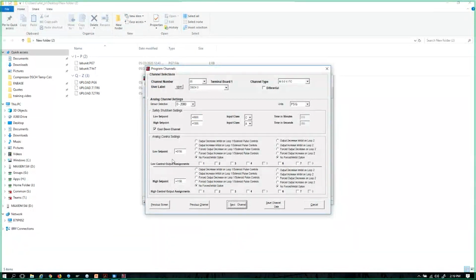Let's use something else. One thing in this channel section that we hadn't talked about is all this verbiage here in these low set point and high set point areas, and I'd like to spend just a little bit of time explaining this to you. The DE-3000 with a one board system has two analog outputs, analog output 1 and analog output 2. Sometimes we refer to an analog output as a loop. It's a current loop, so the terminology is pretty straightforward here. This also affects the solenoid pulse control, if we want it to.